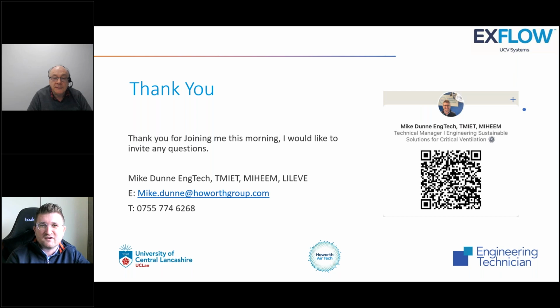Yeah, I'll give some background. When I spoke to Malcolm about the air change rate and energy saving - in the old document from 2007, we were allowed to use belt and pulley arrangements in our fans, and we aimed for 25 air changes because of that. When the new HTM was written and we moved to EC plug fans, belt fans were completely abolished, so he reduced the air change rate. The idea was that with a belt and pulley fan arrangement, we'd set it up at 25, and as the belt slackened and decayed it might drop to 22, 21, 20, but it would never cause a microbiological issue in the operating theatre, because someone like us would go in, change the belts, and it would be back to 25 air changes with no problem. Now there are no efficiency losses in a plug fan or EC fan, because it runs at full tilt forever.